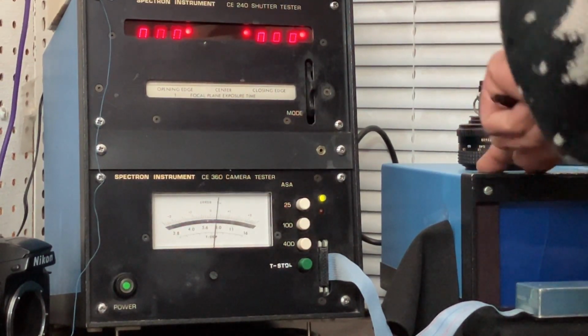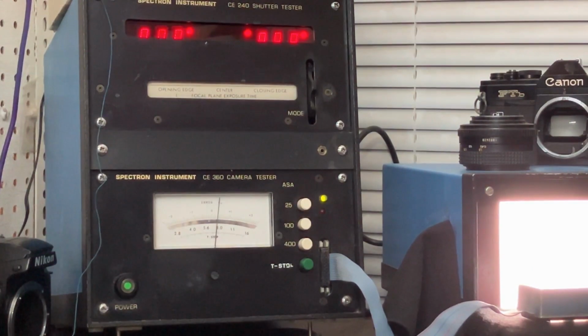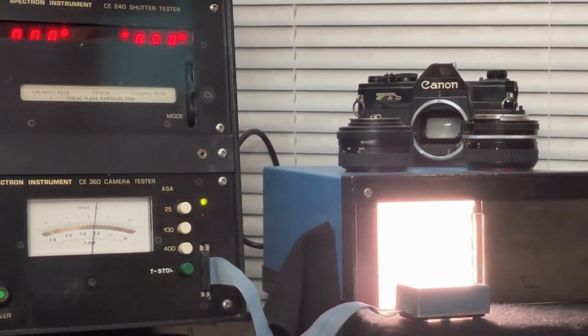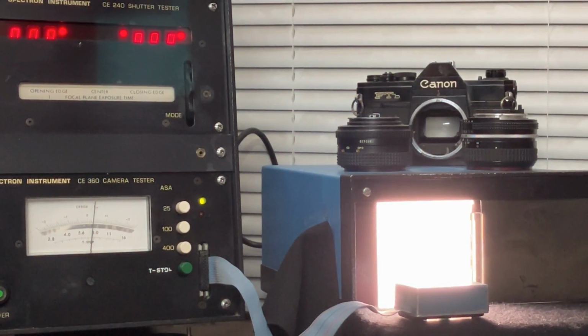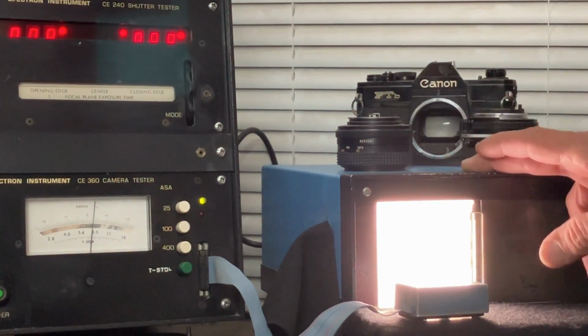So when you fire up the light box, it is just a powerful light source. That's all that is. And the light source right there is a full sunlit day at noon: f16, 1/125 of a second, sun's overhead. That's the brightest setting that most cameras need. If you want to go higher, we have another instrument that goes to EV 18, but we've never found a need for it. It's nice that we can check there if somebody wants to shoot everything at a 4,000th of a second or 8,000th on a film camera. We may use that just to confirm, but this will show us what we need to see anyway to confirm that the 4,000 is accurate. And so it's linear, cameras are linear. So anyway, EV 15 is a 1/125 at f16.